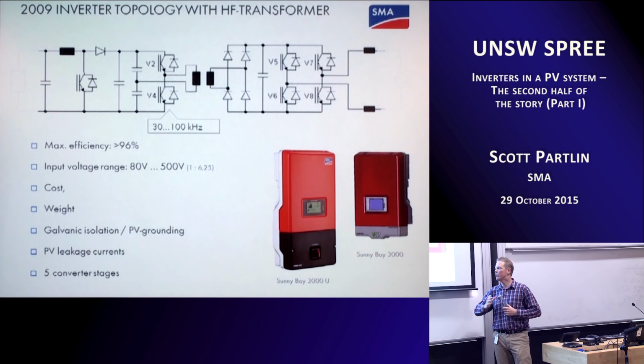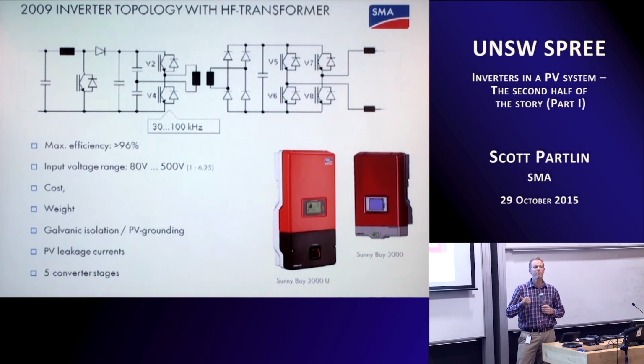A lot of this push came because of thin film modules which required grounding, but also some PV module manufacturers requesting that their products be installed with the negative pole grounded, which if you have a transformerless inverter is not possible, because in that case you would have a direct short from the AC side to ground. Hence this inverter, which is no longer manufactured, and no one wants this sort of thing.